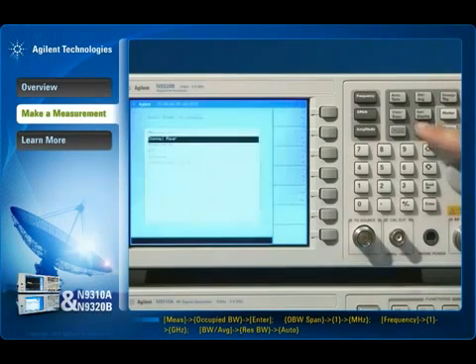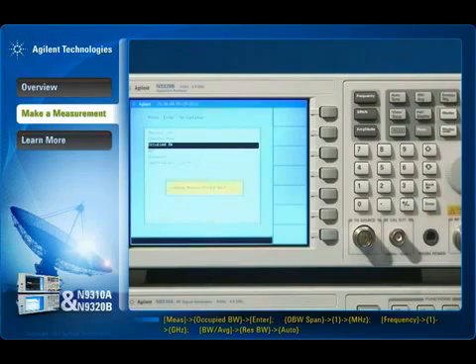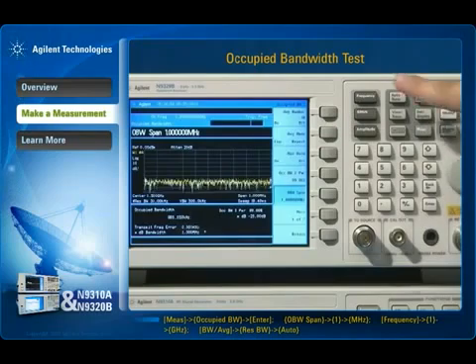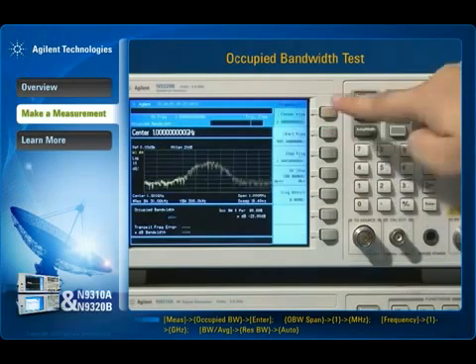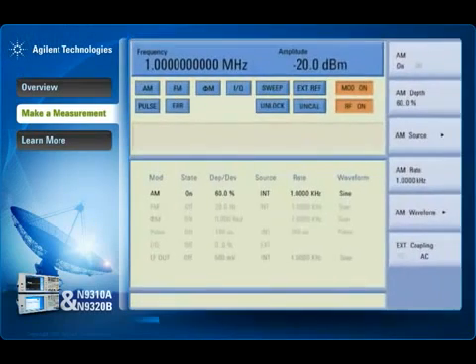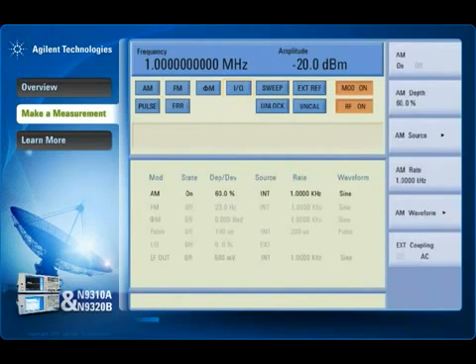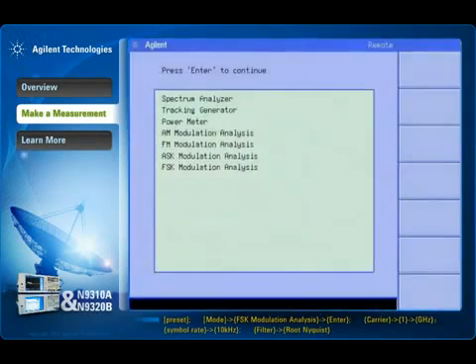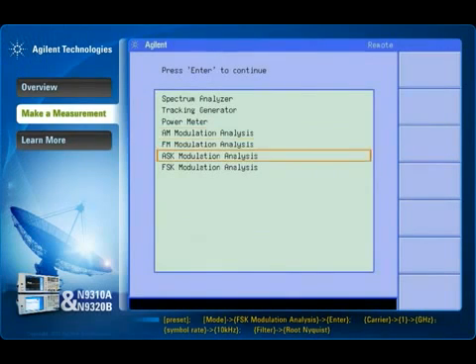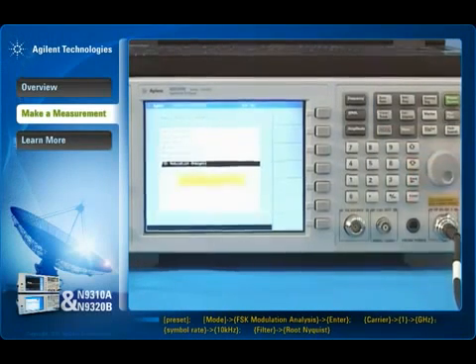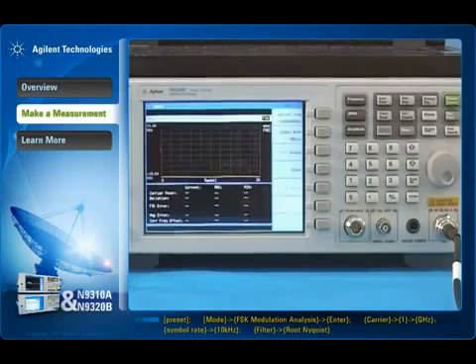The power suite not only shortens the learning curve, but also helps ensure the accuracy of the test setup. Now we change the configuration to produce an FSK signal. The N9320B option DMA supports the demodulation of ASK and FSK signals and also provides readouts for the baseband symbols, RF waveforms, ASK/FSK errors, and eye diagrams.